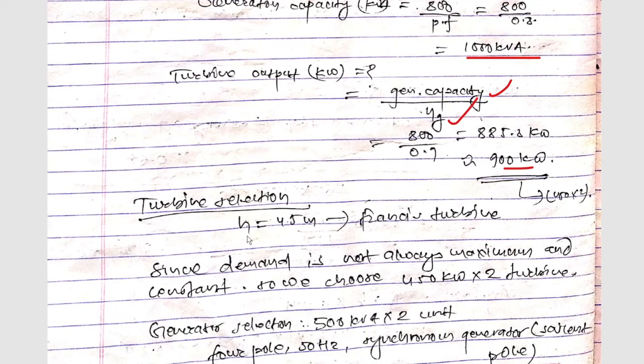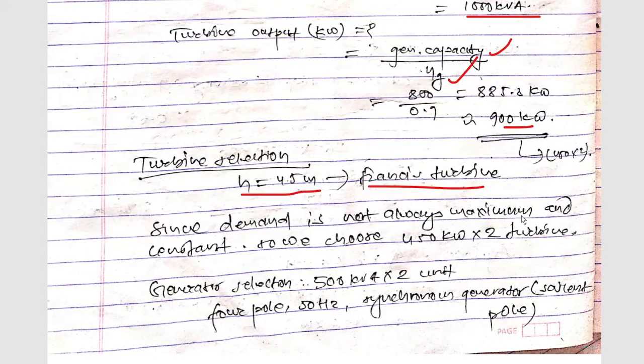So here turbine selection: for head of 45 meter range, the Francis turbine can be selected. And since the demand is not always maximum and constant, so each 450 KW into 2, since this is 900 KW, so two turbines are selected each of 450 KW. And generator selection, so you can select a generator as 500 KW into 2 units and that is a four pole 50 Hertz and that will be synchronous generators or salient pole type.